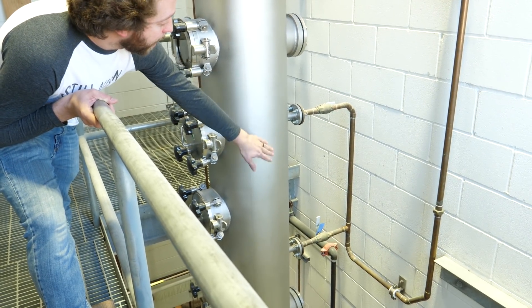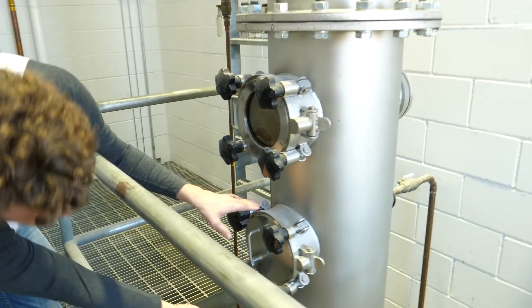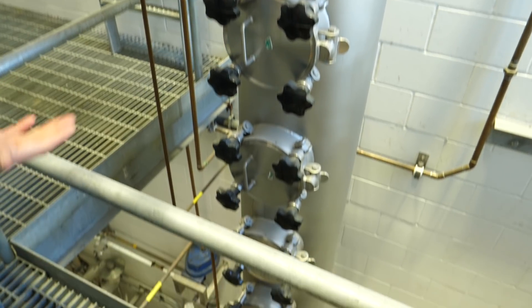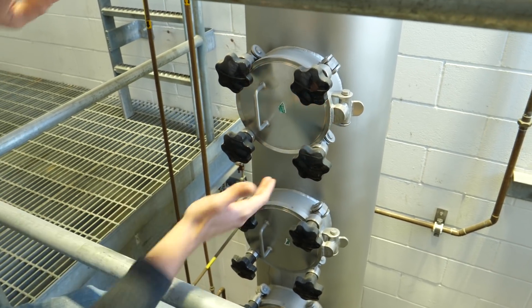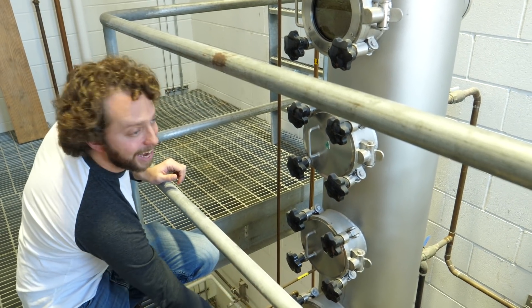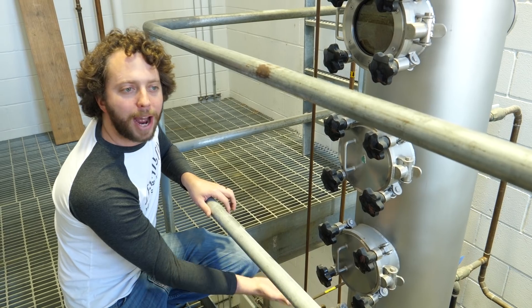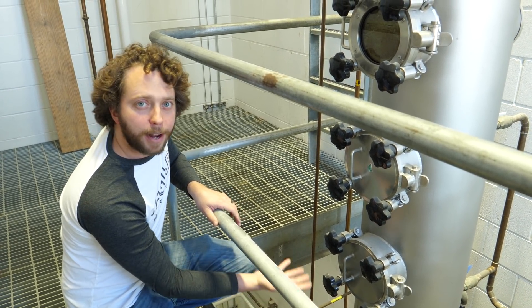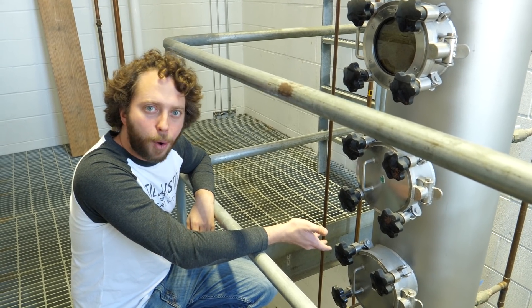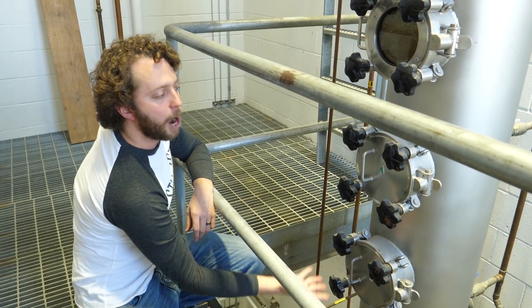Right now we have six fermenters and we typically do two fermenters in a day because we have a three-day fermentation, so we'll do two cooks in a day and get our six that we're constantly rotating through. That said, if we needed to we could do about six in one day in a 24-hour session — we would have to triple our grain intake and our production team would have to have a lot longer days. Right here there are these two pipes, and this top one where the valve is open, you can see the beer is pumped in right here. These windows are blocked off because that's where the most pressure comes in. The grain will come in and fill, and as it does it cascades down. Between each of these windows there is a series of plates that aren't completely flush on the inside — it's much like Plinko — so that the grain has to cascade down, slowing its fall. In the meantime steam is pumped in from the bottom, and the temperature around here is going to be around 180 to 190 degrees, which is the sweet spot for evaporating that alcohol out.